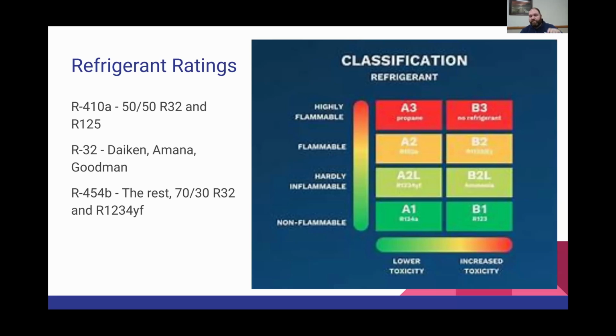Let me back up. Our 410A that we've been using since 2010 exclusively was a 50-50 mix between R32 and R125. Mixing R32 50-50 with R125 made it move from an A2 classification to an A1. So the R125 was acting as a fire suppressant inside of it.